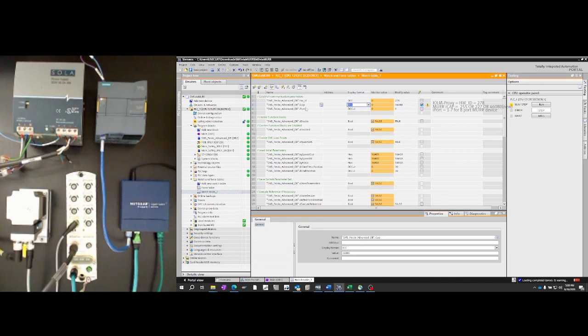The last piece of information you'll need is the IPort. Since I'm connected to X0, you'd think that I would put in a 0 value here for IPort. For all MURR standard and Pro Remote I/O blocks, the port numbering that's on the physical unit is not what you'll put here. Port 0 or X0 will actually be IPort 1. So this is a 1 base index, not a 0 base index. So I have all of these preloaded.